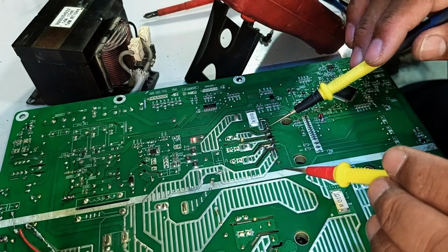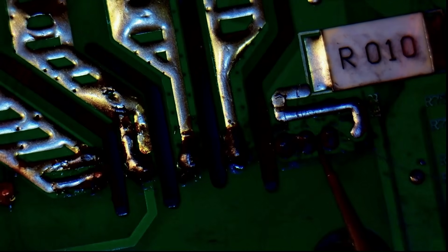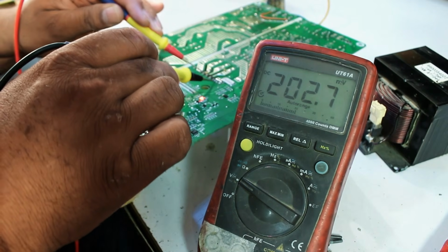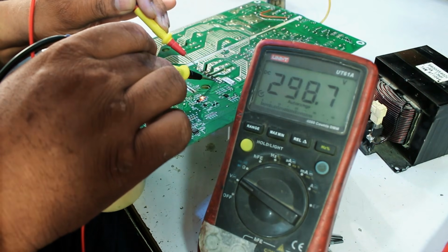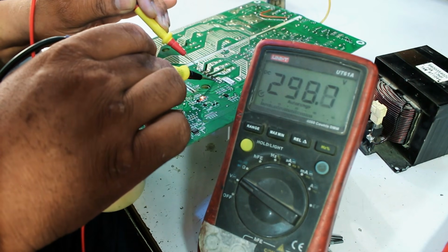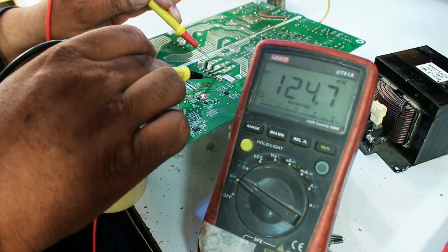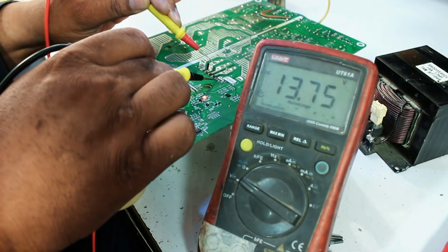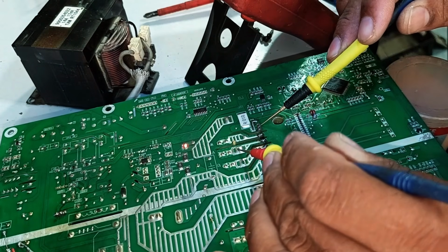Now we will check the voltage on the IPM. We will connect the probe here, one on negative and one on positive. Here we are getting 298 volts DC on the positive side. Now let's check the U, V, and W outputs. This is not okay, on this one we are getting 13.76 volts.